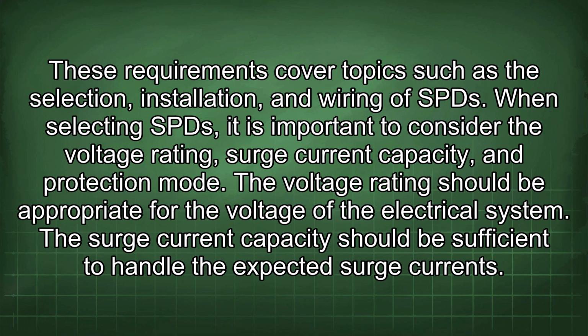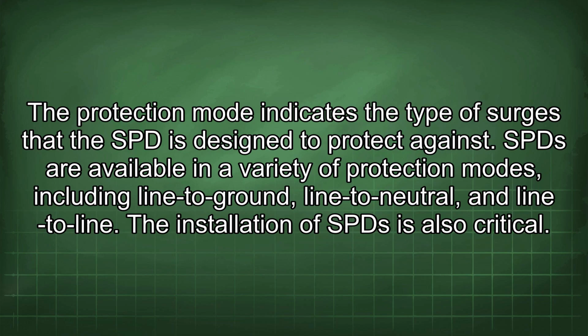The voltage rating should be appropriate for the voltage of the electrical system. The surge current capacity should be sufficient to handle the expected surge currents. The protection mode indicates the type of surges that the SPD is designed to protect against. SPDs are available in a variety of protection modes, including line to ground, line to neutral, and line to line.